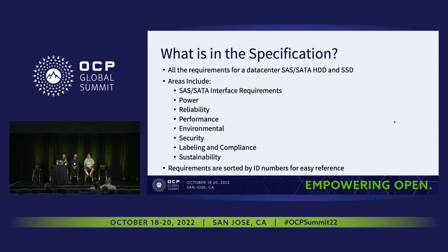In the environmental section, we specify how a drive performs in environmental conditions, including the thermal, the humidity, and also the vibration conditions, as Zakia just introduced, right? The drive operating in our chassis will be sensitive to the acoustic vibrations imposed by the fan speeds. We also define the performance perspective, right? How does the drive performance look? How much degradation are we allowed under different conditions? Same thing for temperature and humidity.